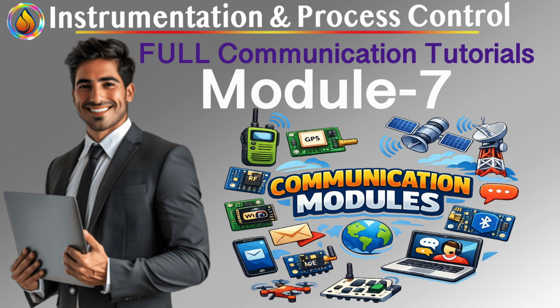Terminators, non-negotiable. Exactly. H1 is a transmission line. Transmission lines must be terminated correctly. Foundation Fieldbus requires exactly 2 terminators, one at each end of the main trunk. The tutorial states this clearly. Terminators are placed at each end of the pair to eliminate reflections, not 1 terminator, not a terminator on every spur. Exactly 2. Why? Because reflections at 31.25 kbps distort signal edges, break synchronization, and cause sporadic communication loss. Most H1 problems in the field trace back to missing terminators, extra terminators, or terminators placed on spurs instead of the trunk. This is not tuning. This is physics.